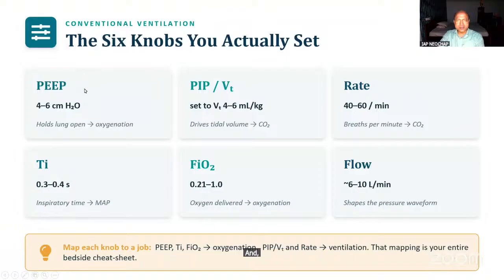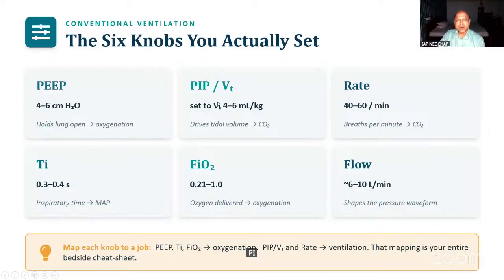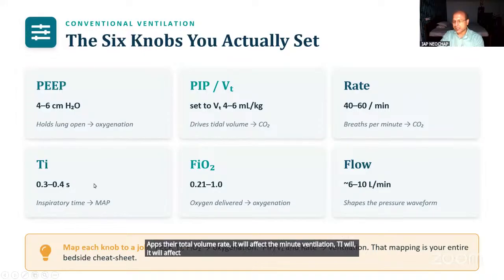And how do they affect the ventilation? PEEP affects the FRC and it affects the oxygenation. PIP affects the tidal volume. Rate will affect the minute ventilation. TI will affect the MAP, and also it will affect the oxygenation. FiO2 is easy to understand. And flow waveform: if you have a high flow, it will become a square wave, more MAP. A low flow will become a triangular one, which will have less MAP. So flow also affects. This is the last thing we interfere with. Usually we play around with PIP, PEEP, rate, TI, and FiO2.